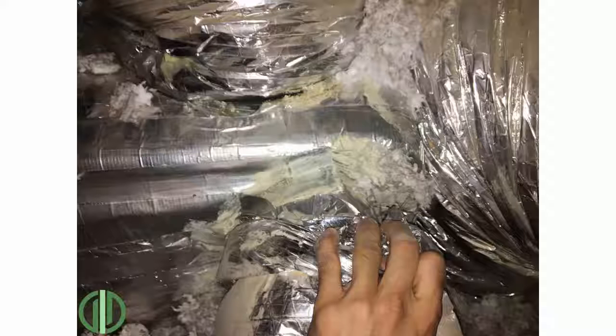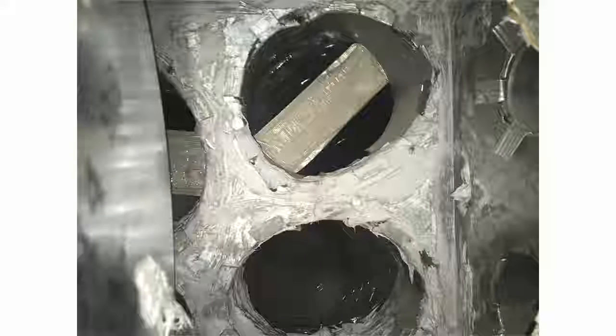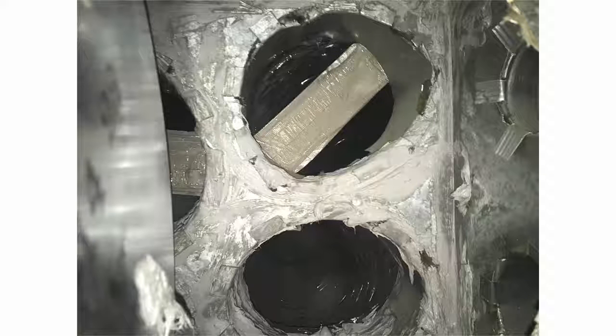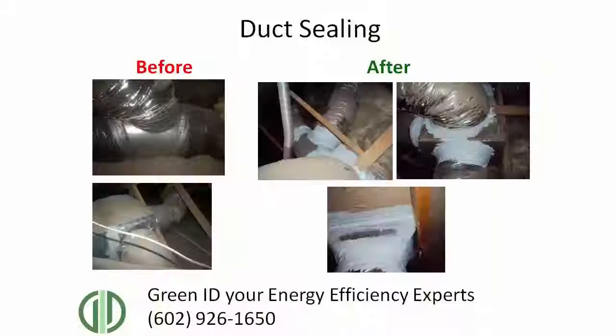You can see in this photo the original installers just used duct tape to seal the registers and seal the ductwork up. This causes a lot of leakage every time the air conditioning comes on. You can see the before photos just have duct tape around the registers as a sealant. We want to use a product called mastic. It is like a cast and hardens to let no air through any cracks and splits in the ductwork, so the air goes all to the rooms that it's supposed to go to rather than in the attic.